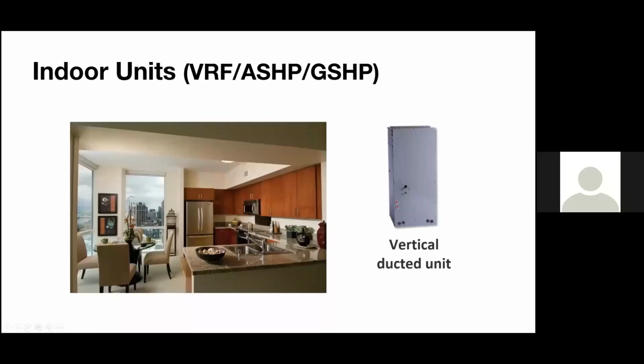And then this is something that's very similar to an air handler that we might be used to. This is kind of the American version of this type of fan coil. But this is a vertical ducted unit, also known as a multi-positional ducted unit. What's nice about these is they have 3 configurations. You have an upflow, you have a downflow, and then also you can put it on the side and have a horizontal flow. So what these are great for is high rises or multifamily buildings where you can take out that existing water source heat pump that's end of life and shove that right into the wall right there. And then all you need is about 18 inches in the front for clearance, and then you're good to go. So choose your orientation, good to go.